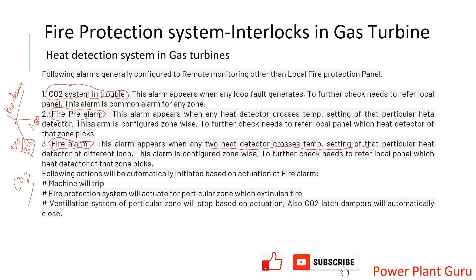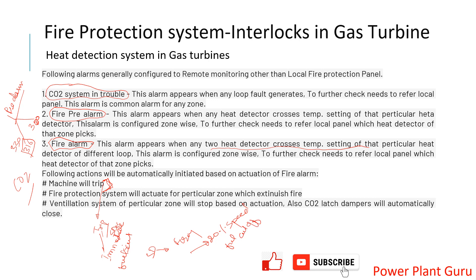The fire alarm will actuate the CO2 flooding system. When CO2 flooding actuates or a fire alarm occurs, multiple actions happen simultaneously: the machine will trip to prevent further fuel supply and additional damage. It is important to understand the difference between a trip and a shutdown. A trip means an immediate, instantaneous fuel shutoff. In a shutdown, the machine continues firing and fuel continues to flow until the machine reaches 20% speed, then fuel is cut off. A fire alarm triggers a trip — immediate fuel valve shutoff.